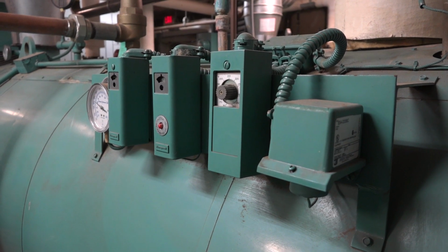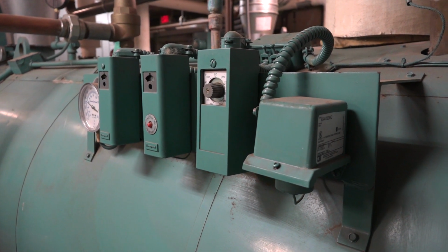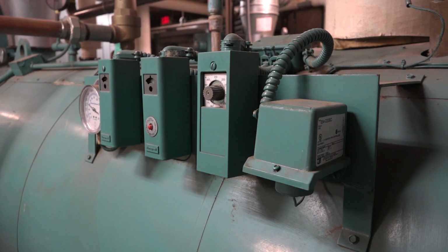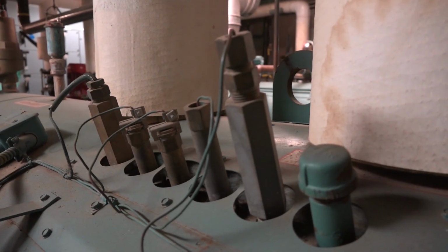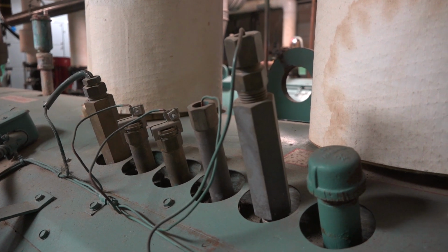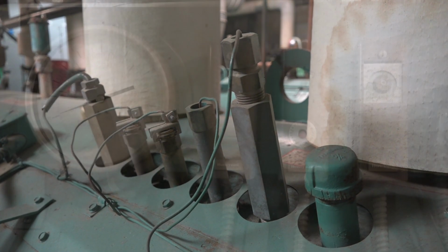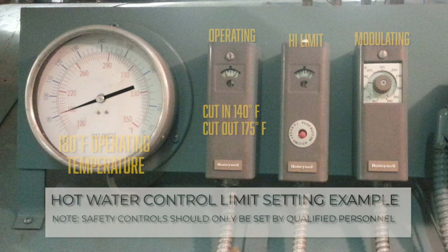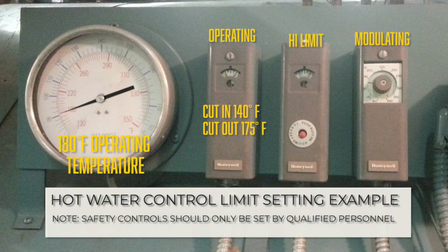As mentioned, the controls are different, as a steam control relies on pressure to make or break a circuit, whereas hot water systems utilize what is commonly referred to as an aquastat. Aquastats are simply a control that works much like any other thermostat, and it depends on a submerged sensing bulb that can be set to open or close accordingly at a set temperature of the fluid. So for example, a system needing 180 degree operating temperature, the operating control may be set to cut in around 140 degrees and then to drop out at around 175 degrees. This would account for any creep in the temperature after the burner does cut out.